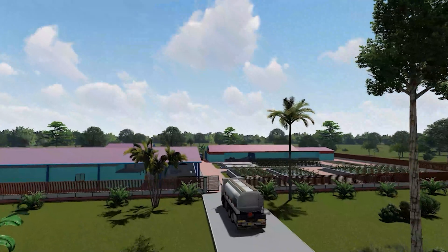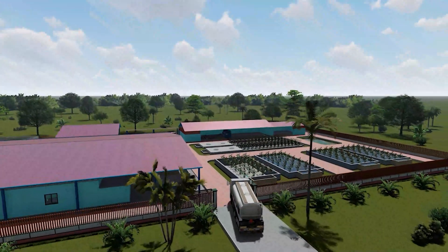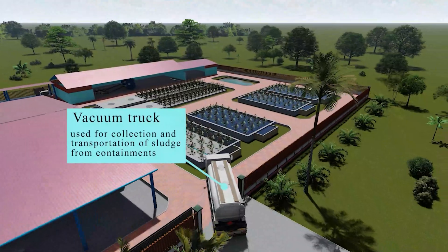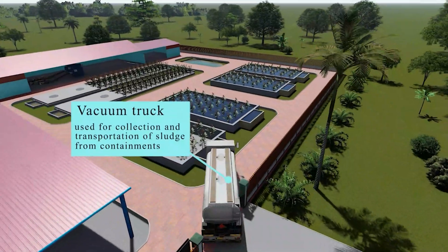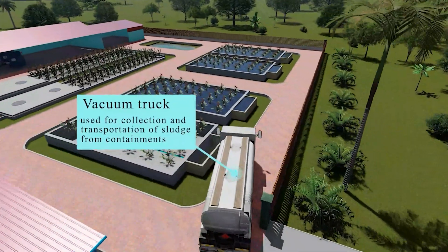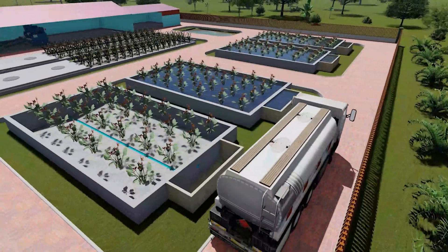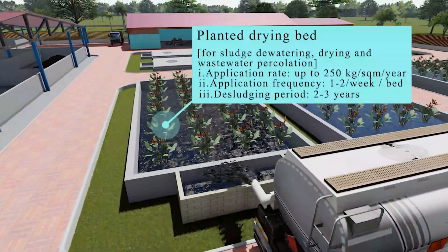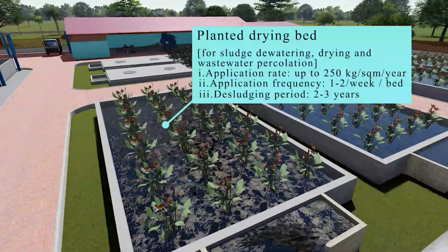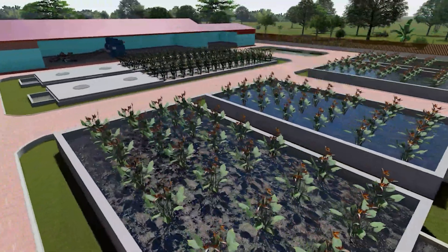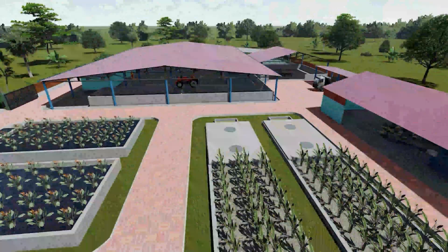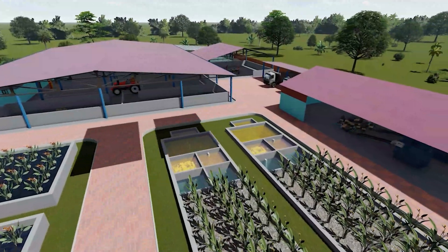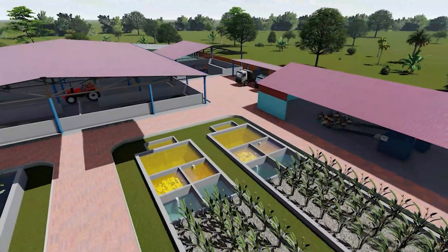Fecal sludge is systematically collected from a variety of sources. By using mechanical vacuum tankers for collection and transportation, the sludge is then directed to planted drying beds. These planted drying beds are engineered with porous media, such as sand and gravel, and are further enhanced with emergent macrophytes to facilitate the drying process.